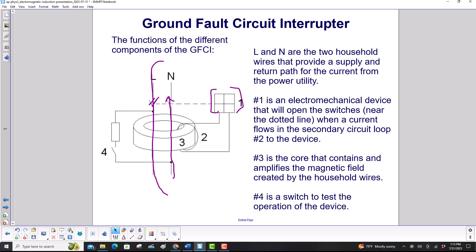Number one is your electromechanical switch. That will open these switches here that will interrupt the current flow. That happens when you have a current flowing in the secondary loop here. The secondary loop is wrapped around this metal core, but it's not electrically touching it. There's insulation between it and the core. And what's the core doing? It's amplifying the magnetic field and containing it. And that magnetic field is caused by these wires. You have current flowing, you have a magnetic field. And number four, this is where we can test the device to see if the switch is working.